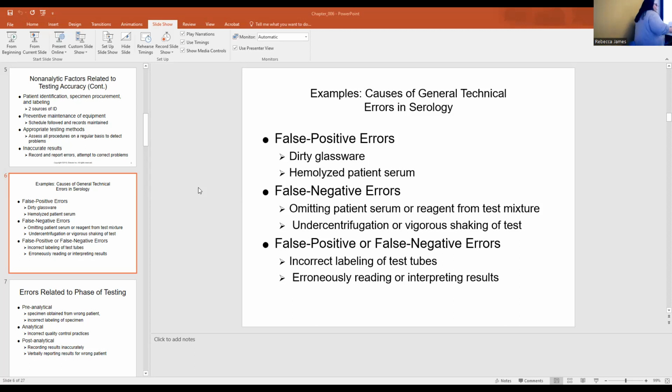And then you're probably thinking, well, why couldn't you change your reagent before you did all that maintenance and stuff like that? Well, the reason why is these reagents are super expensive. Super expensive. So I'd rather do all this stuff before I did that. So change your reagent and then rerun your QC again. And guess what? It's still out. At this point, there's nothing else you can do.